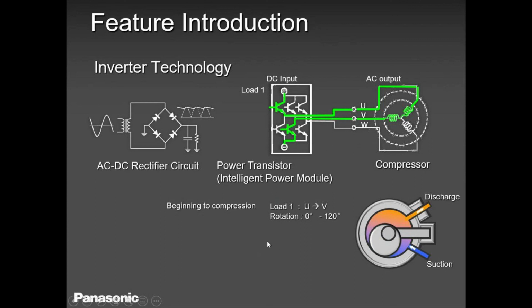In this case, I put a very simple slide. There is not much load, only 2 people there. So the compressor is hardly running. Okay, and then when it sees heavy load based on the sensors, it tells the compressor to ramp up. That's pretty much how this inverter technology operates. So when you find out that your compressor is not ramping up or ramping down, the first thing you should focus on is the sensors. And if your sensors are in good shape, then chances are you are low on refrigerant. Okay, so sensors talk to refrigerant, refrigerant talks to sensors, and then sensors talk to the compressor.